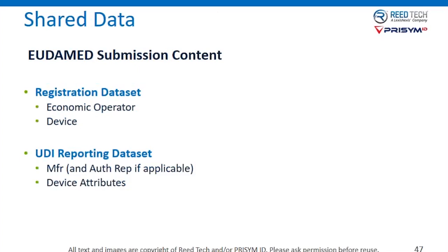Noteworthy is that there's some shared data that is electronically managed and submitted to the EUDAMED, and information about your economic operators and the device needs to be collected early on, and part of the registration needs to be submitted to EUDAMED. And then as part of your reporting, which is a second submission, a lot more details about the manufacturing organization and also the device attributes need to be submitted.